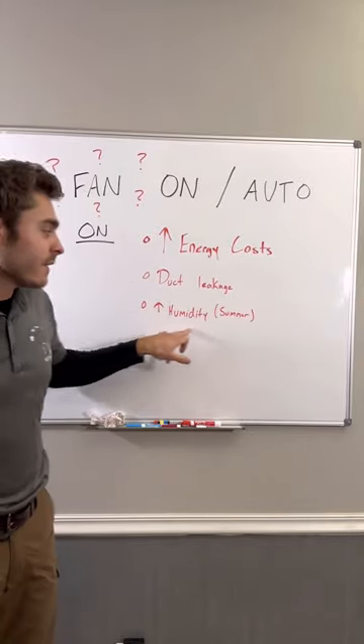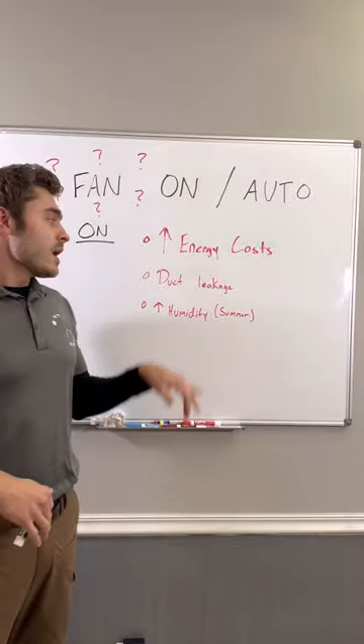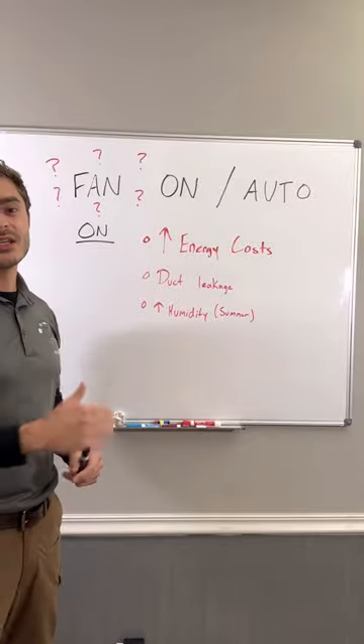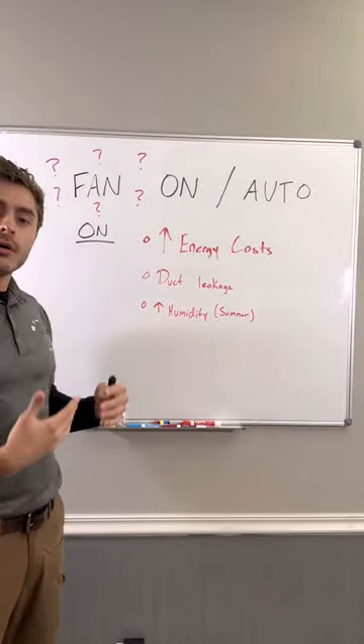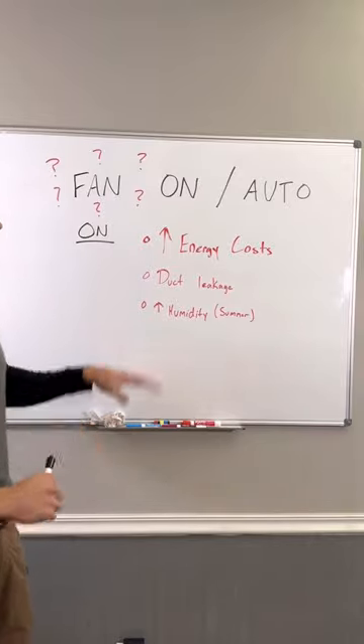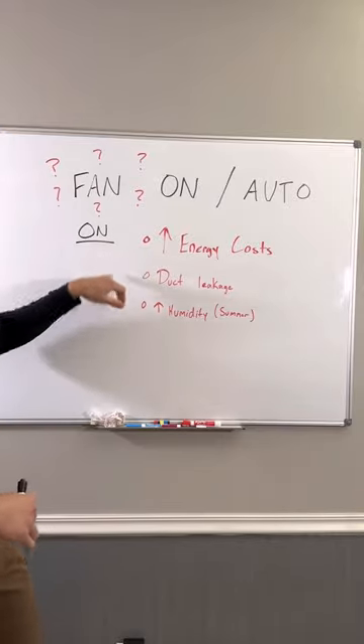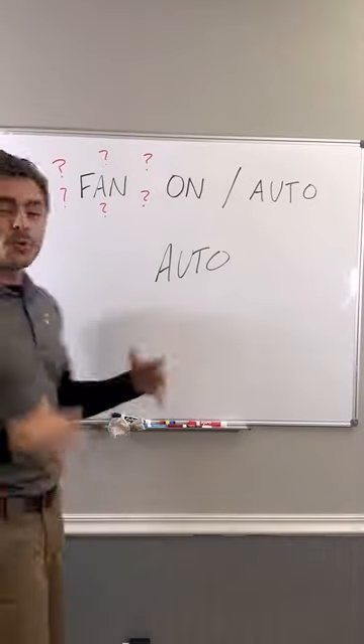And the last thing is humidity. If you have standard equipment (most people do), if you leave the fan to the on feature in the summertime, you're actually going to be reintroducing some of that humidity back into the house. As the air goes across that coil that's supposed to be removing that moisture, it picks it back up and puts it back in the house. So not a great idea in the summertime on basic equipment and not a great idea if you have ductwork in the attic or crawl space.